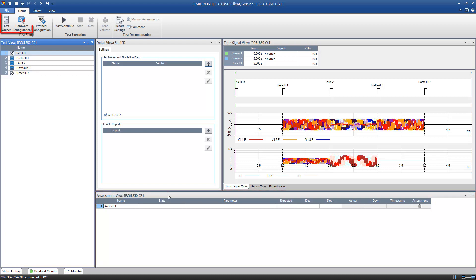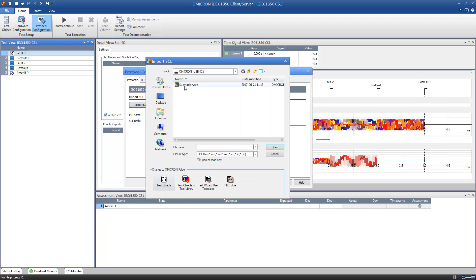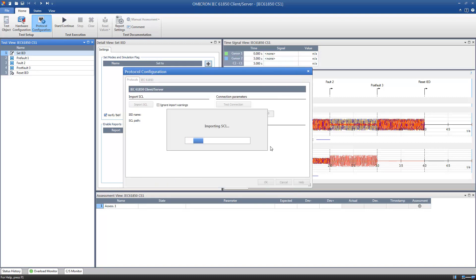In addition to the test object and the hardware configuration, which is common to all test modules within Test Universe, the Client Server module needs information about the communication according to the IEC 61850 standard. This information can be loaded using the protocol configuration. Within IEC 61850 compliance substations, all data is stored in an SCL file. This abbreviation stands for Substation Configuration Language. By loading the SCL file, you can utilize the data model and other information like the configured reports for your test.